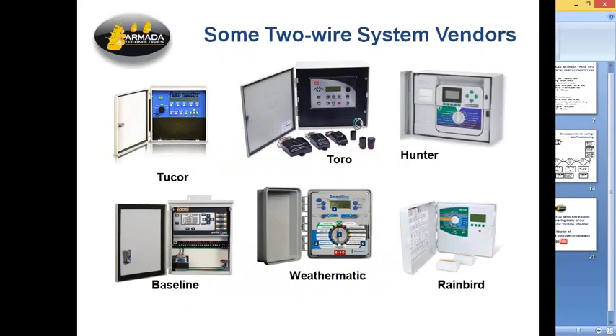You don't necessarily have to take the multi-day training class that these manufacturers offer in decoders to do a little troubleshooting. You can go and sit in a Hunter class for 3 days. They'll tell you how to program it, how to troubleshoot, how to design the system, everything. We do a little class in troubleshooting that takes less than an hour, and today we're doing this in 30 minutes, and we're not doing detailed troubleshooting, but it's the 80-20 rule. You have to get a leg up on this thing.